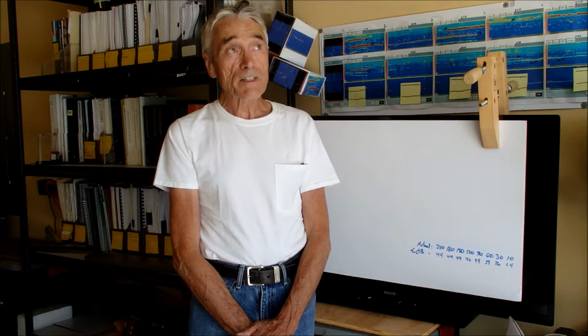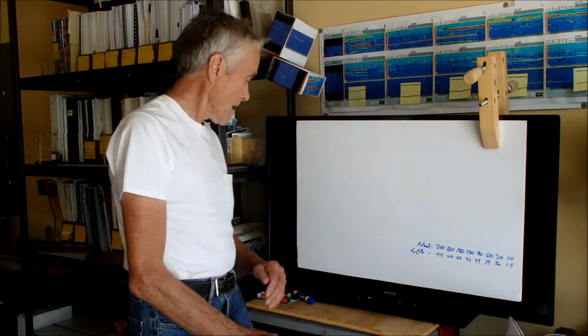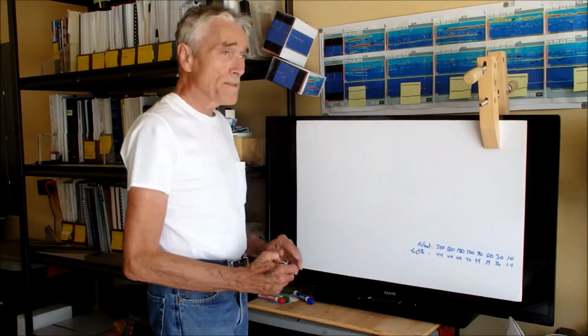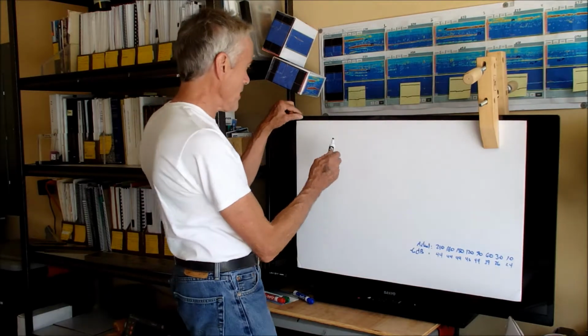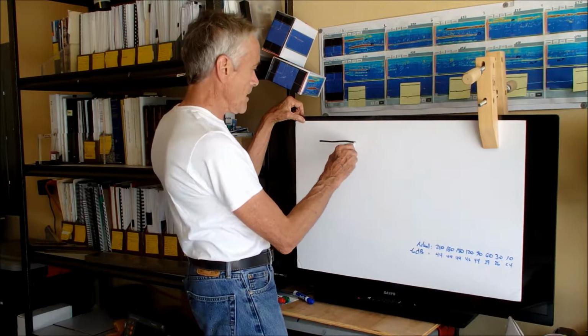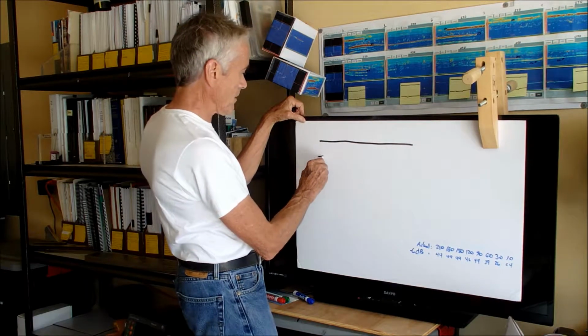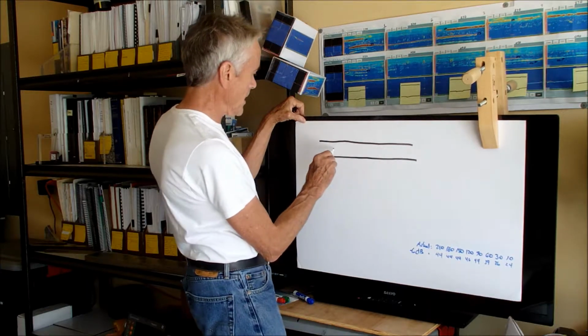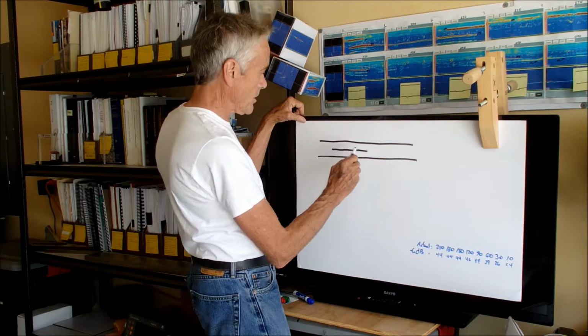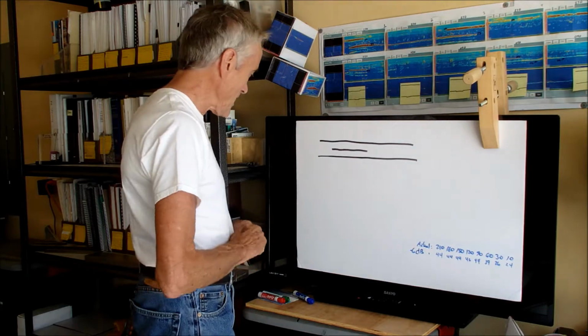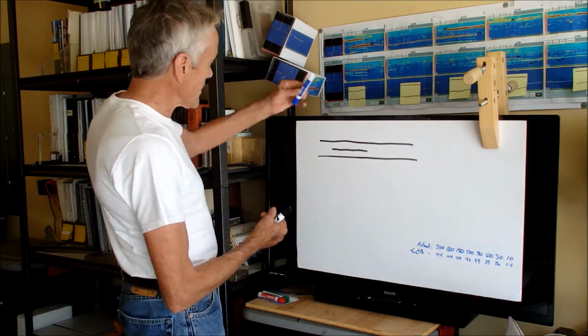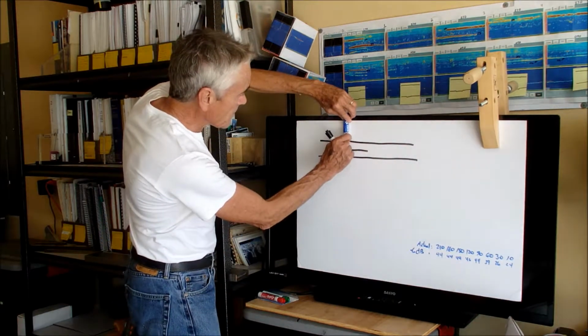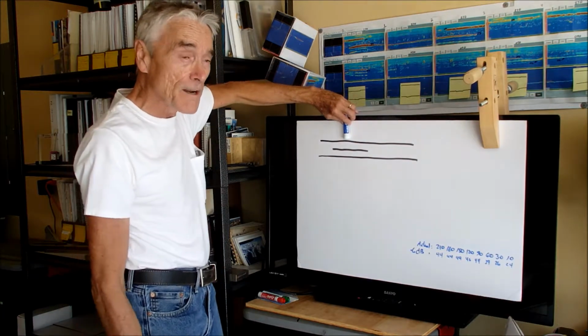Okay, so 6 dB drop flaw height sizing does not work. But there are a couple of cases where 6 dB drop sizing works. One case would be in the case of a big lamination. Let's say this is the outside of the material and this is the inside of the material. And you had a large lamination that was larger than the size of the transducer. Let's say this is your transducer, so there's your surface area of the round transducer.